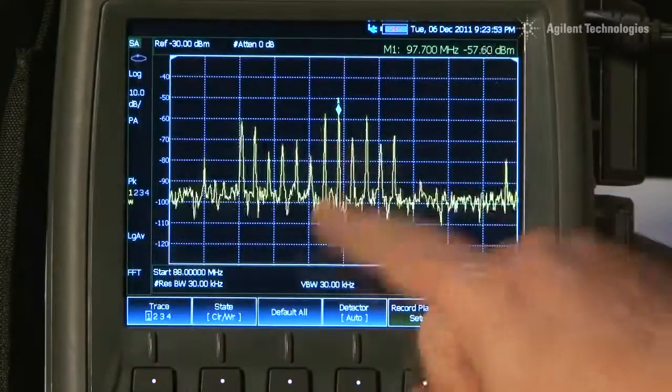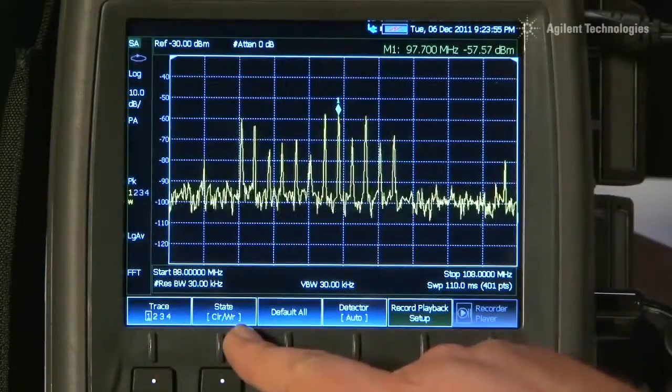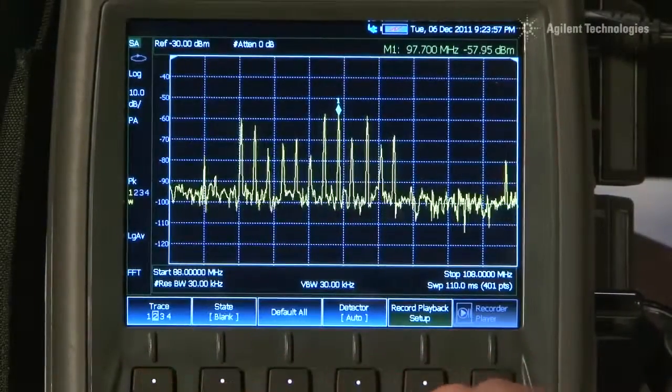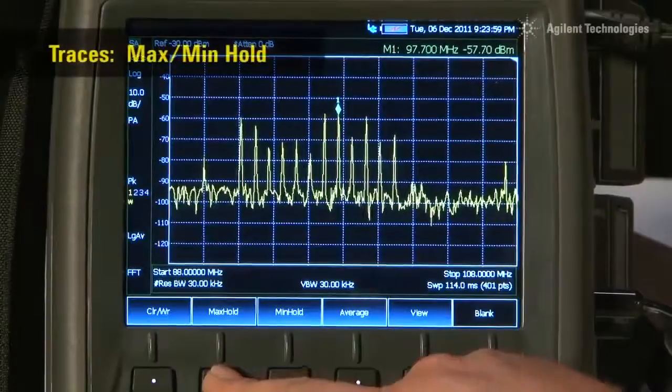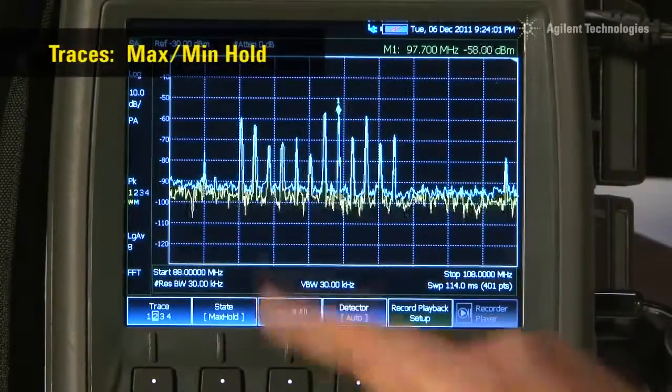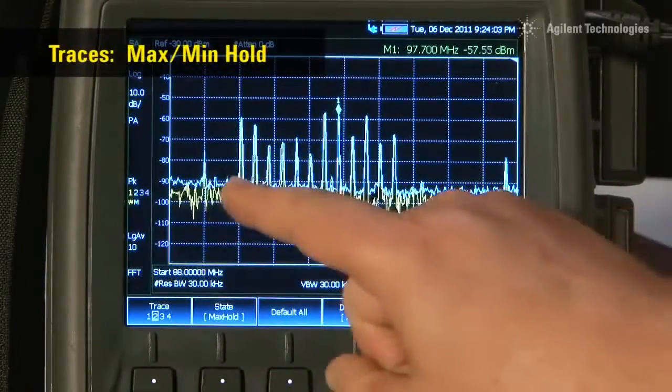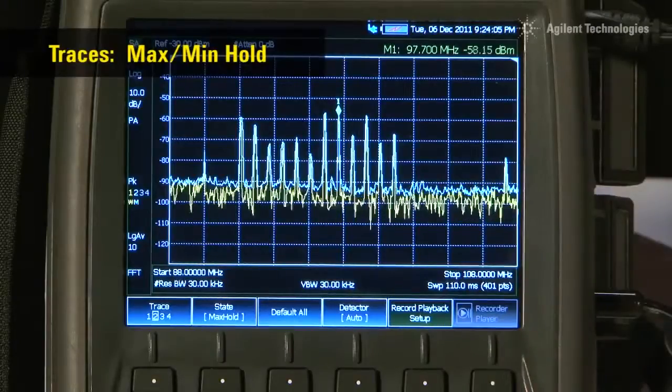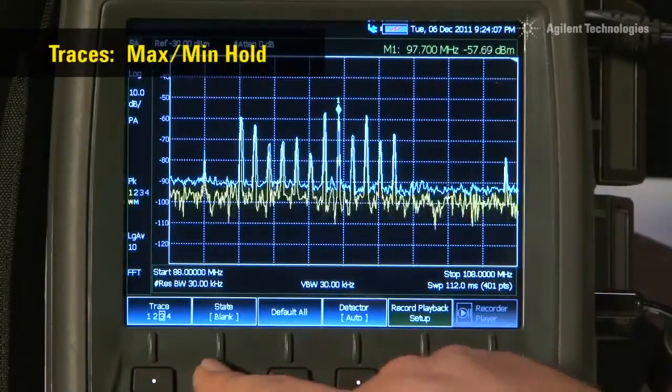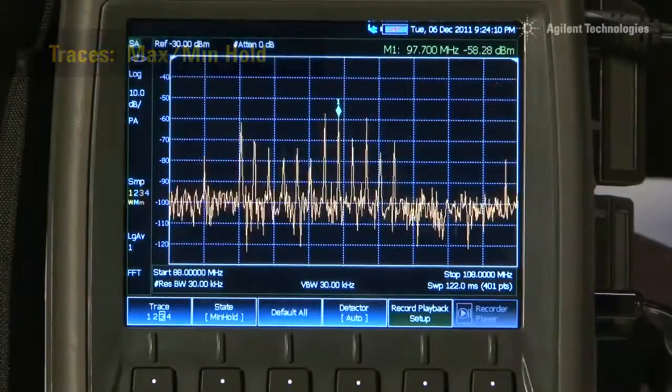If I press the trace button, you can see that trace 1 is here in yellow, performing a clear write operation. If I select trace 2, currently set to blank, but set it now to max hold, you will see in the blue or white trace it is storing the maximum value of the signal. And we have two more traces. Let us turn on trace 3 and set that to min hold.